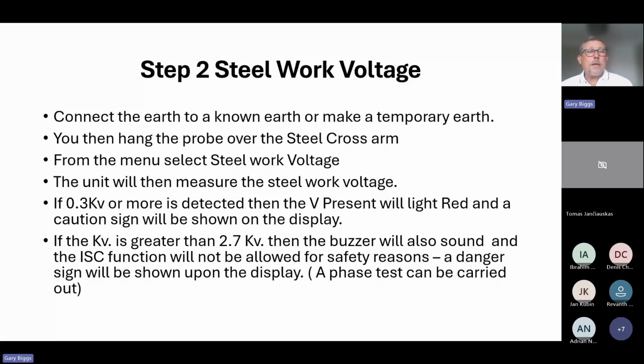So going into the unit, we look at the menu and we select from the menu the box that says steel work voltage, and then you hit OK, and the unit will then measure the steel work voltage. If 0.3 kV or more is detected, then the V present light will light. So if more than 300 volts is present, that's when the light will light up, to give you a caution, to tell you that there is voltage there on that cross member and you need to be aware of it.